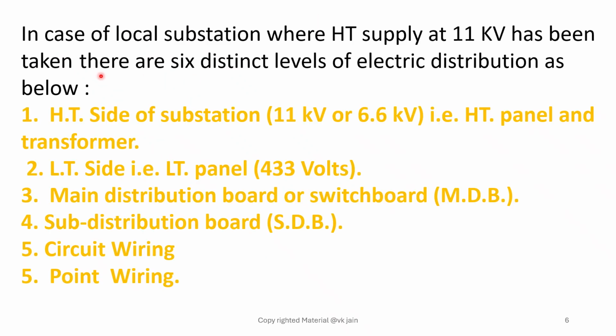Friends, in case of a local substation where HT supply at 11 kV has been taken, there are 6 distinct levels of electric distribution as detailed below. First one is, after metering, it goes to the HT side of the substation. It may be 11 kV or 6.6 kV, where 6.6 is very rarely used. That is the HT panel and transformer. Then second, the LT side, actually it should be the MV panel, MV side, which is rated 433 volts.